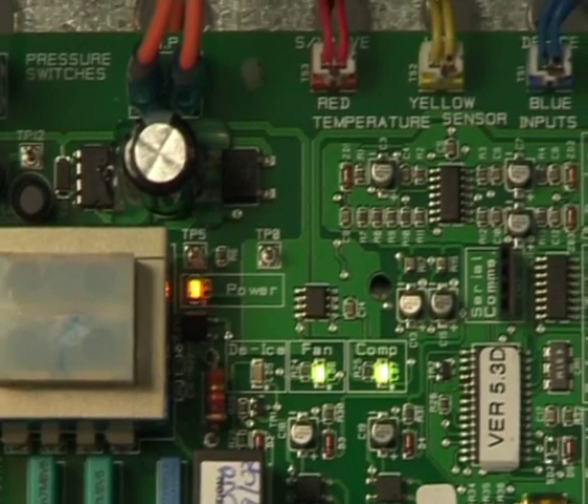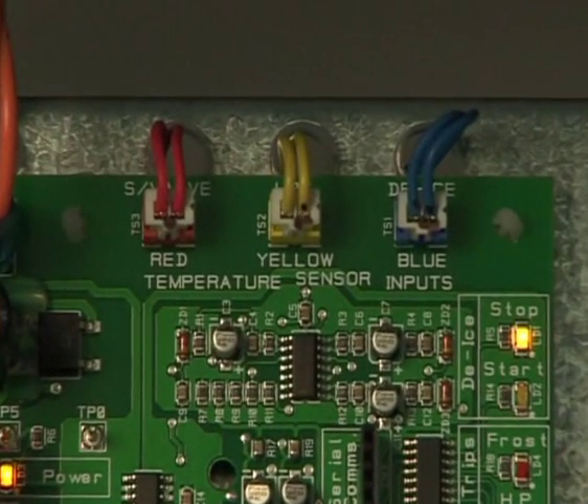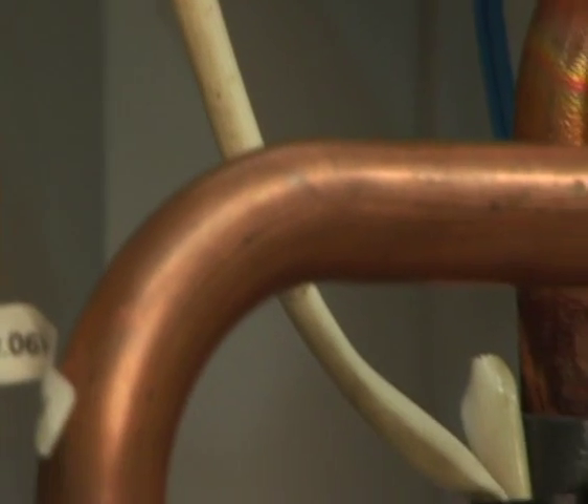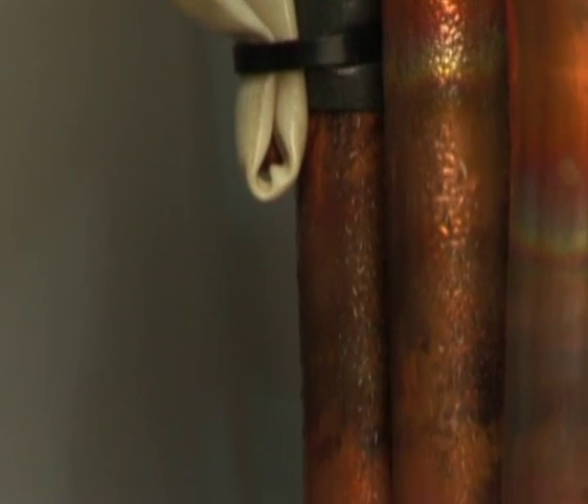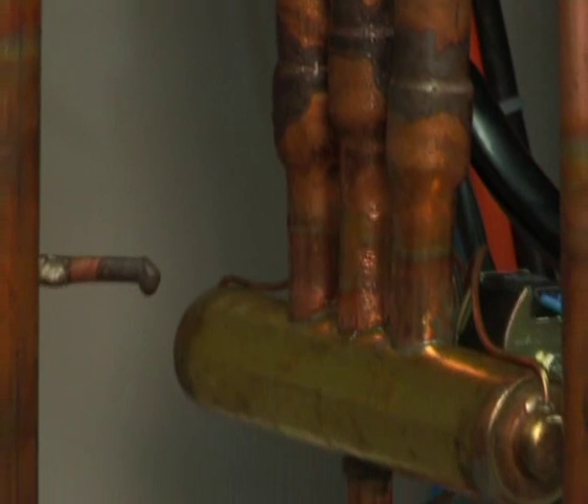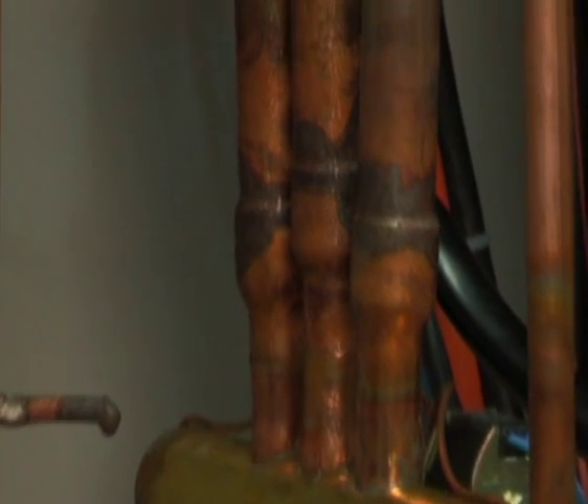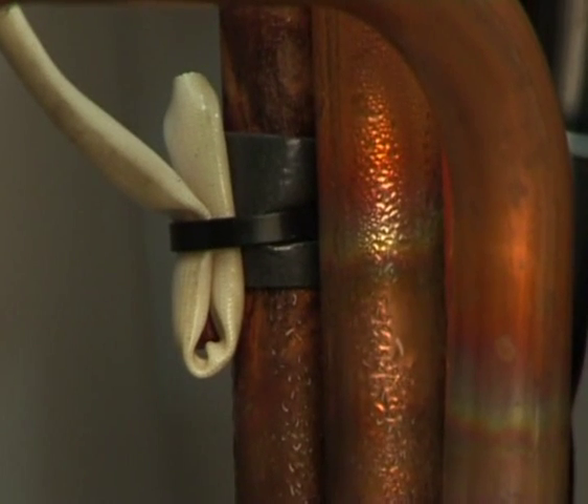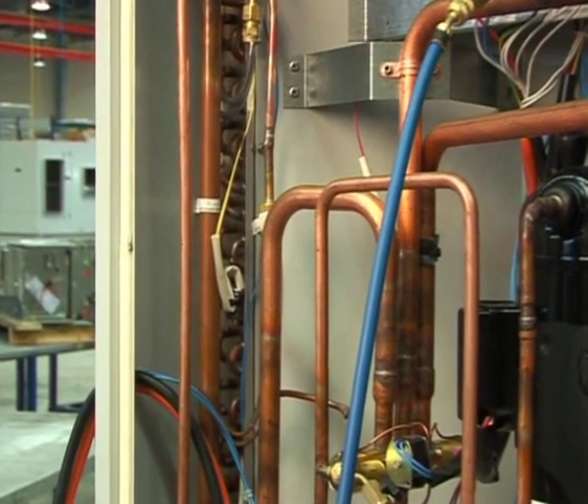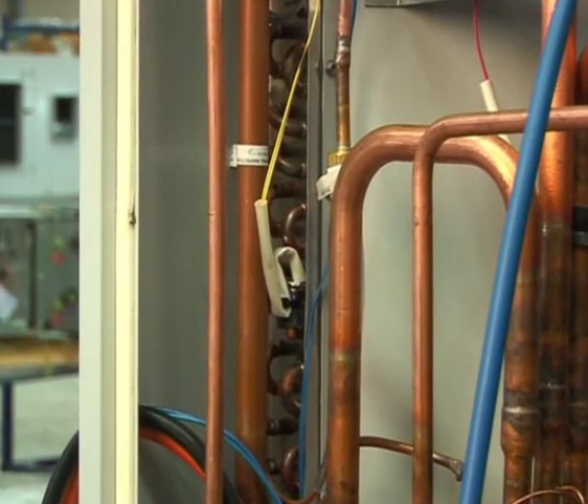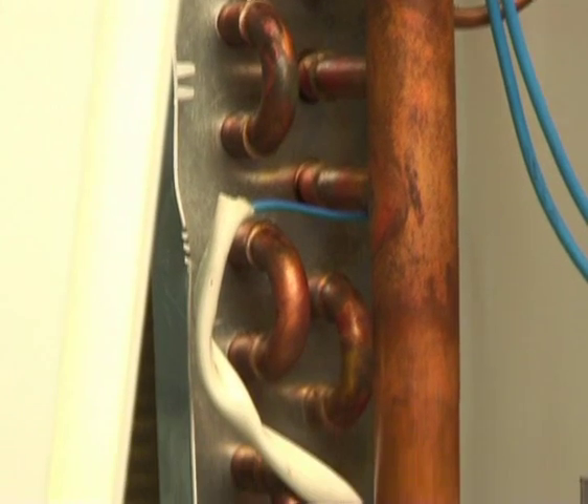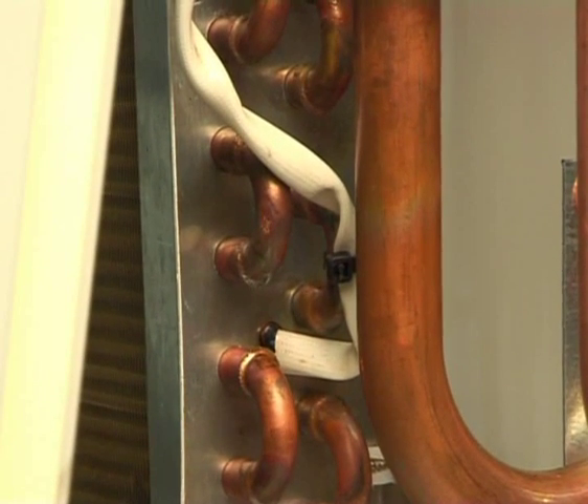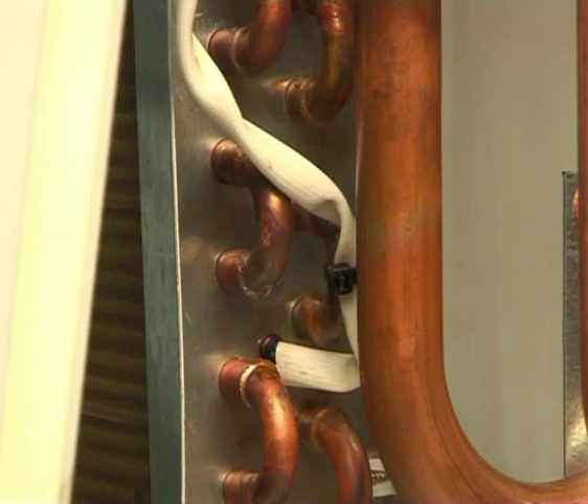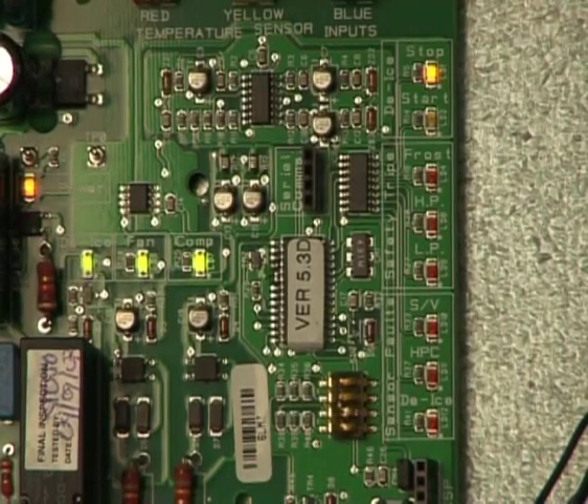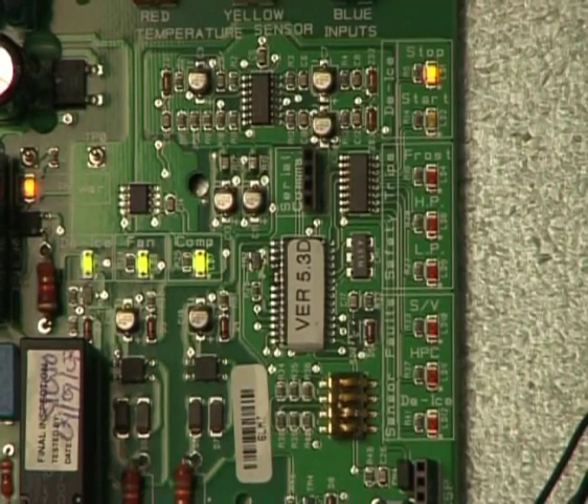System monitoring and fault detection is by way of 3 colour-coded individual sensors. Firstly, the red lead service valve sensor, which is located in a pocket on the suction line between the service valve and the reversing valve on split systems, or suction line from the evaporator to reversing valve on package units. Secondly, the yellow lead HP sensor, which is located in a pocket on a return bend of the condenser coil. And finally, the blue lead De-ice sensor, which is located towards the bottom of the condenser coil embedded in the coil fins. The OUC also incorporates a series of LEDs that are designed to indicate system status and operation, as well as any possible faults that may arise.